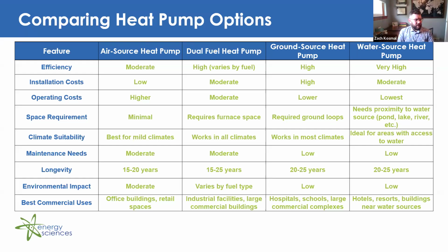So best commercial uses, these are just guidelines. Many of these systems can be applied in wide varieties of commercial facilities, but your air source heat pumps typically found in office buildings, retail spaces, dual fuel in industrial facilities, larger commercial buildings. And then ground source heat pumps are very common for hospitals, schools, and large commercial complexes. And water source heat pumps, commonly found in hotels, resorts, and buildings near water sources.